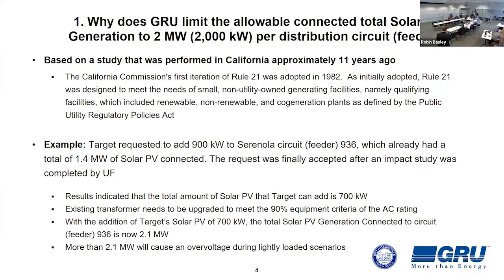About a year ago, we were approached by one of our customers, Target, who wanted to add 900 kW of solar PV on their rooftop and connect it to the distribution circuit they're served from, Serenola feeder 936. We looked at our records and determined that circuit already had 1.4 megawatts connected to it, so 900 kW would put us over the 2 megawatt limit.